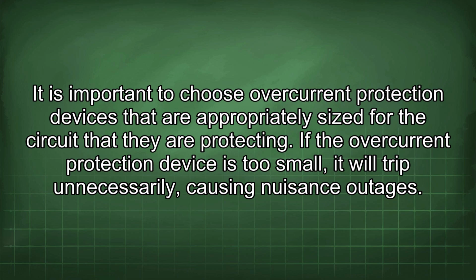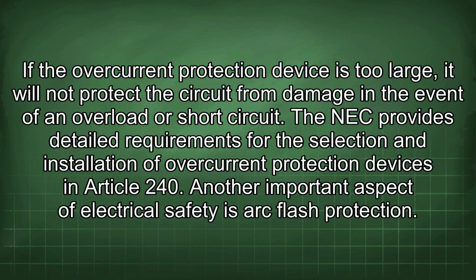If the overcurrent protection device is too small, it will trip unnecessarily, causing nuisance outages. If the overcurrent protection device is too large, it will not protect the circuit from damage in the event of an overload or short circuit. The NEC provides detailed requirements for the selection and installation of overcurrent protection devices in Article 240.